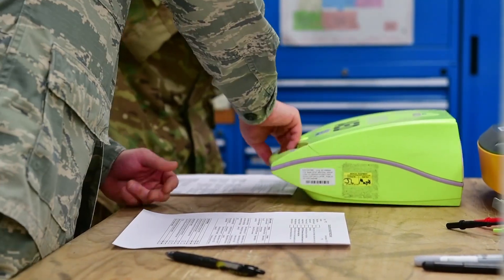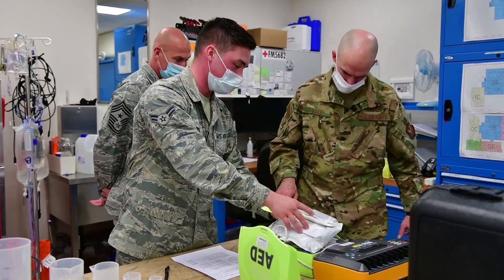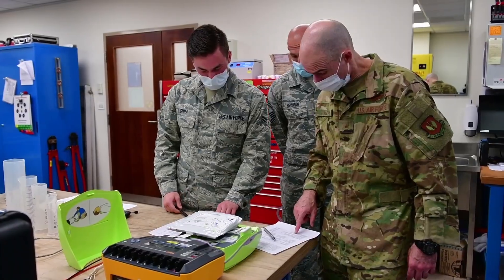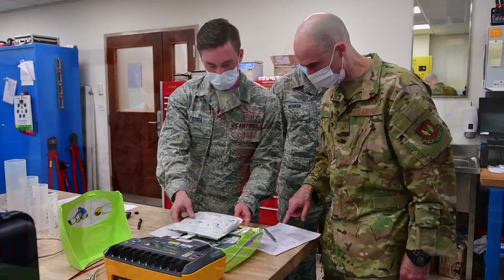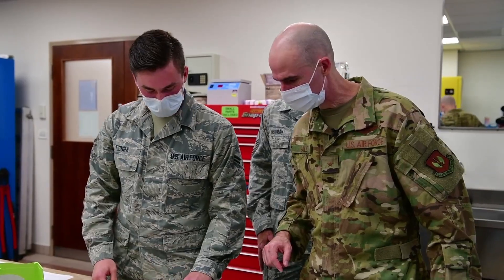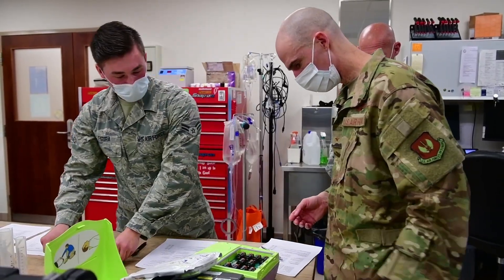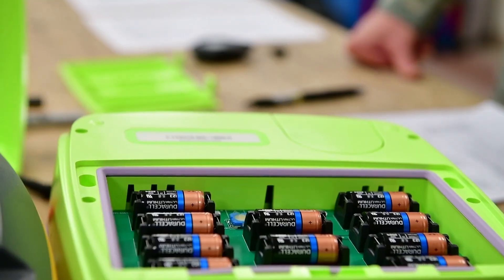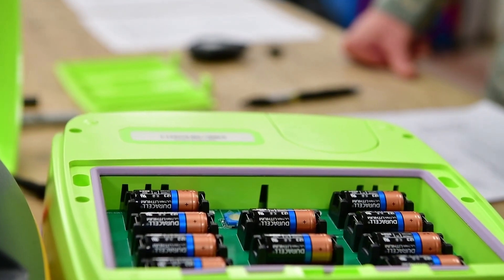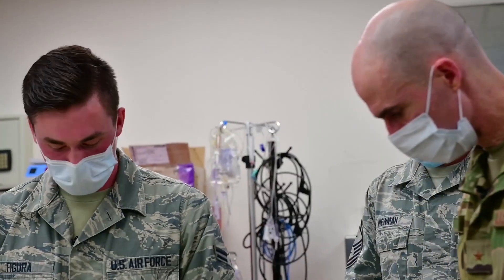We're going to take the unit and do a physical inspection. We're going to look at the pads — this is what connects to the patient. Turn it on and off and verify the green check indicates ready for use. Now we can turn it off because we're going to check the batteries. We don't need to take any out; we just need to make sure that they're not expired. All of these batteries have March 2024. Verified — all batteries are up to date.